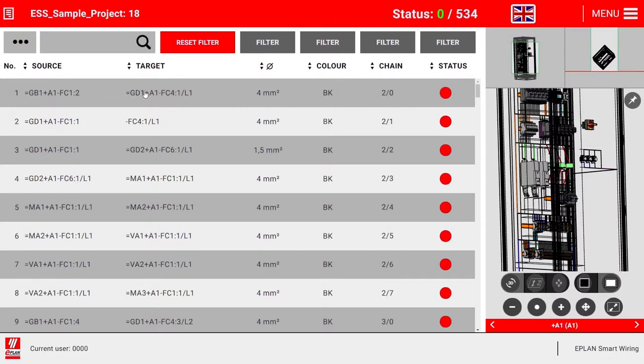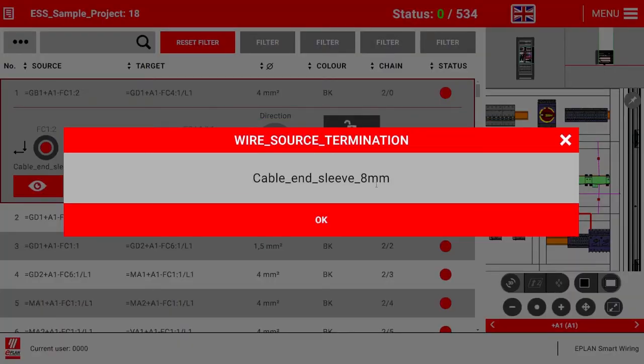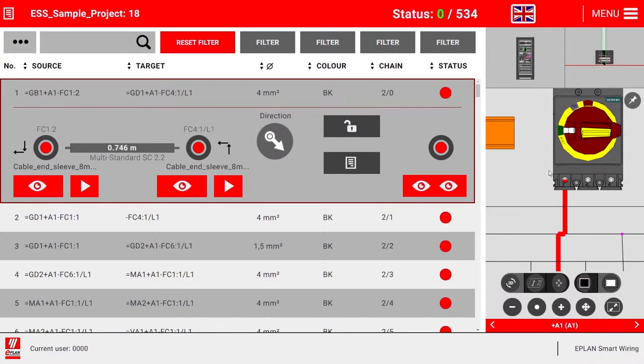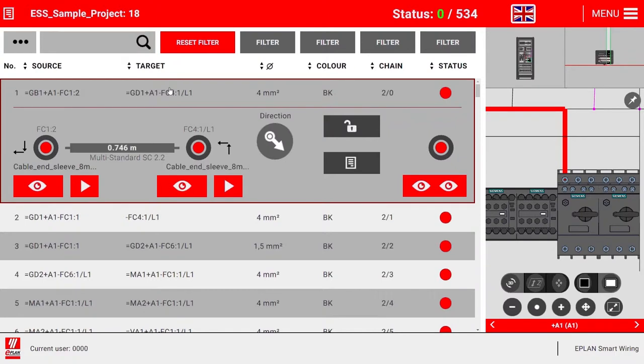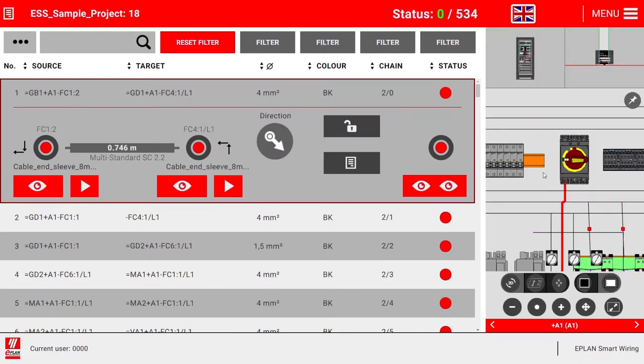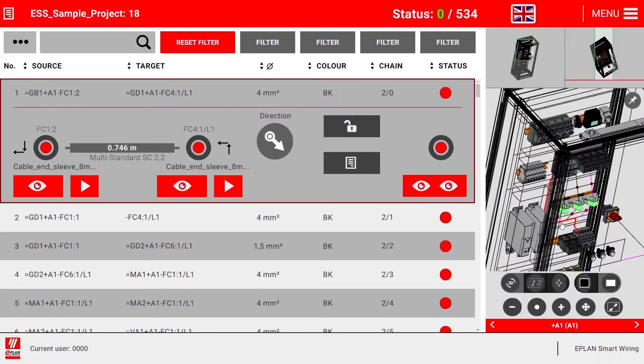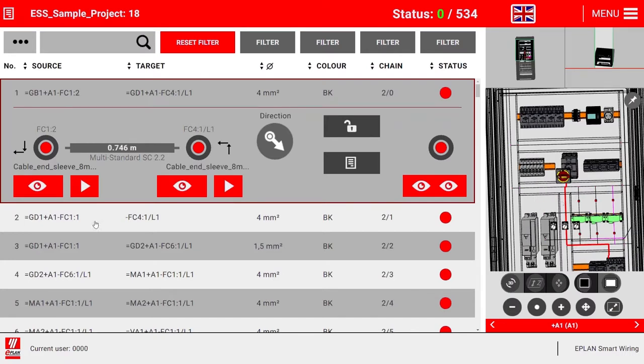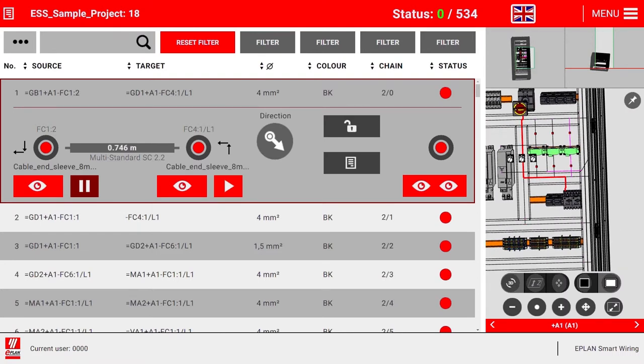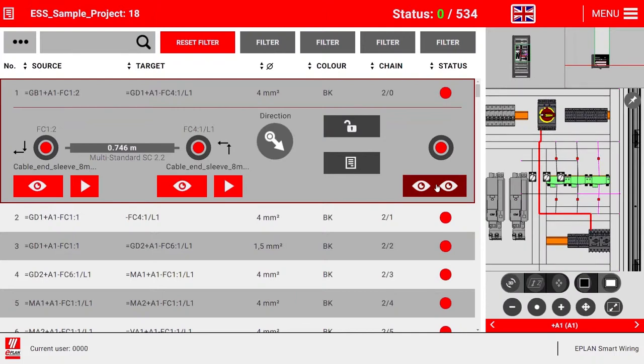I click simply onto a wire. Very quickly you can see here's my source, here's my target, here's the length of the wire I need to cut. The cable end is the 8mm sleeve. If I visualize where it physically needs to go, this one goes to the isolator on the backplate. The target goes onto the section here. I can see the direction I need to move from source to target. Very quickly, if you're still unsure, if you've got a pretty strange view or a pretty long route, there's a little play button that will show the route as it goes around the actual panel, so it makes life a little bit easier. You can click onto the multi-view to see exactly where it needs to be too.